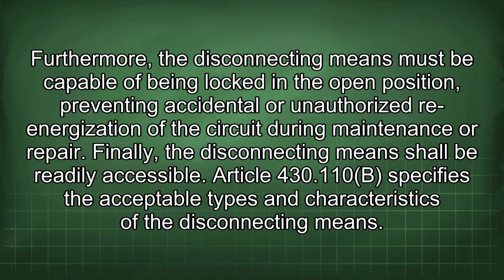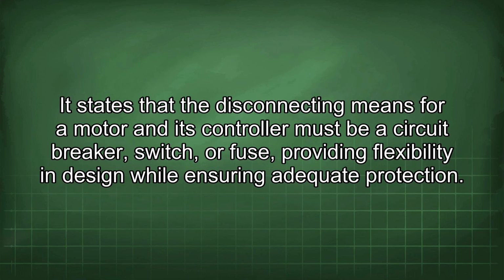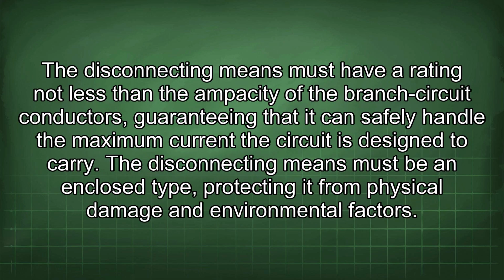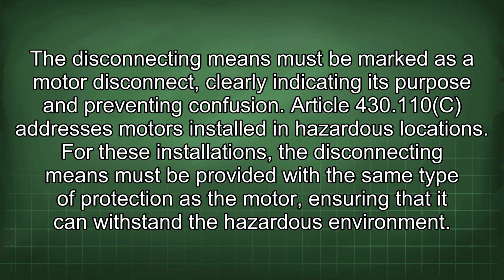Article 430.110b specifies the acceptable types and characteristics of the disconnecting means. It states that the disconnecting means for a motor and its controller must be a circuit breaker, switch, or fuse, providing flexibility in design while ensuring adequate protection. The disconnecting means must have a rating not less than the ampacity of the branch circuit conductors, guaranteeing that it can safely handle the maximum current the circuit is designed to carry. The disconnecting means must be an enclosed type, protecting it from physical damage and environmental factors. The disconnecting means must be marked as a motor disconnect, clearly indicating its purpose and preventing confusion.